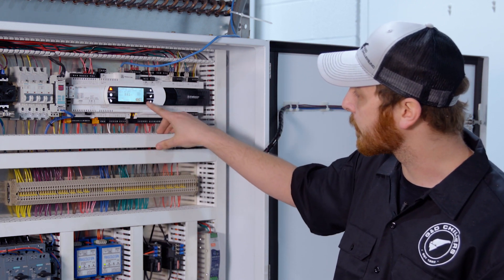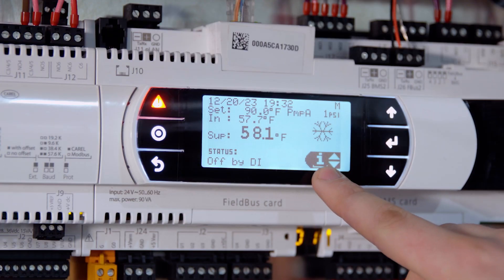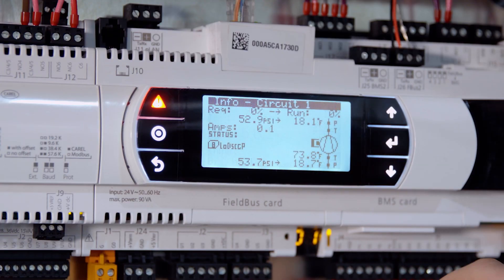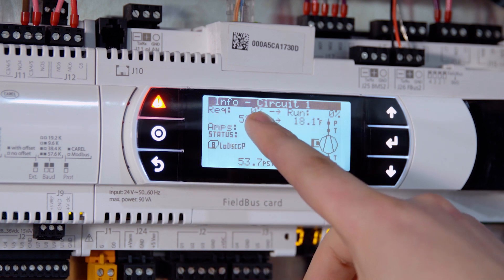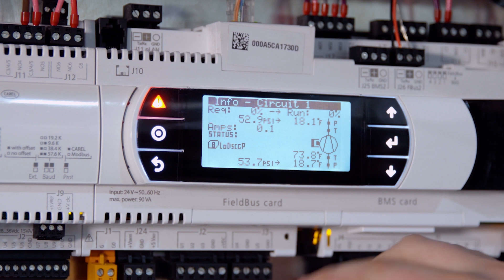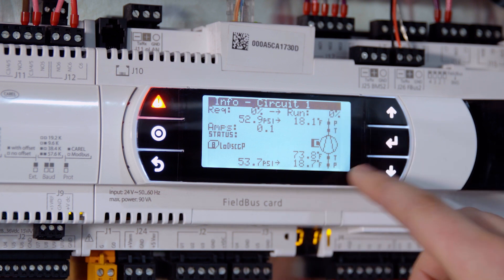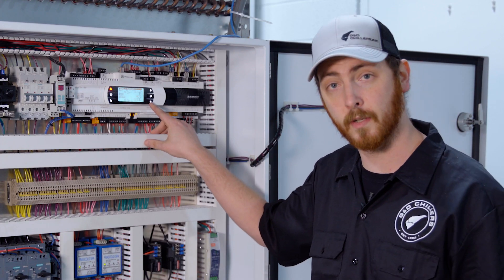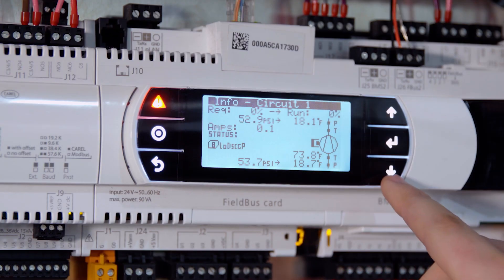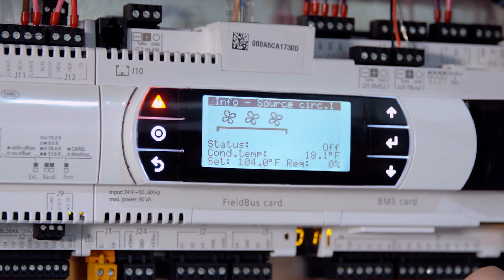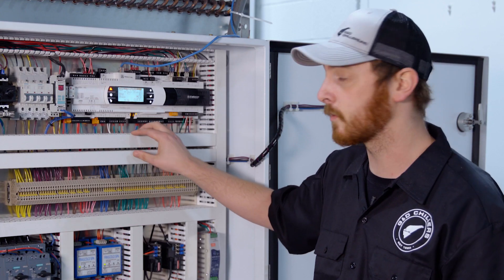If you press the up and down buttons on the Carel controller on the main screen, you'll notice you have an eye icon that'll bring you to your info screens. These tell you really good information such as whether the compressor is running, discharge pressure, suction pressure, and your suction temperature sensor. If you have a dual series with two compressors, you can navigate through all these screens — you have your expansion valve screen — and you'll get to circuit two, which has the same screens.